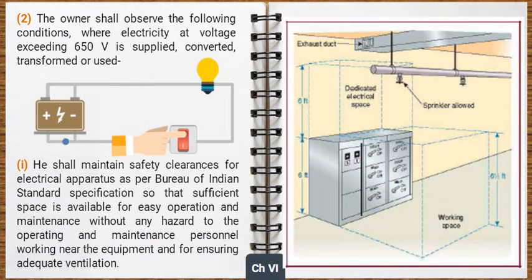He shall maintain safety clearances for electrical apparatus as per Bureau of Indian Standard specification so that sufficient space is available for easy operation and maintenance without any hazard to the operating and maintenance personnel working near the equipment and for ensuring adequate ventilation.